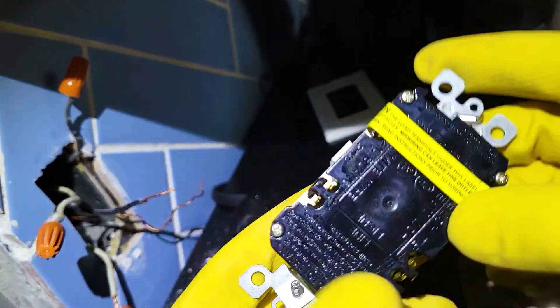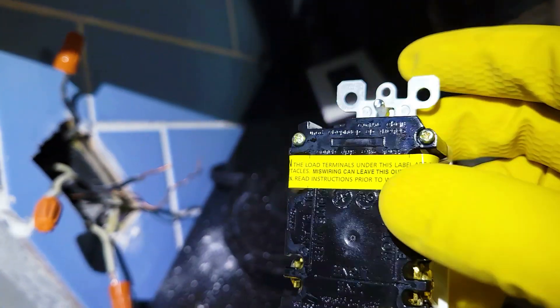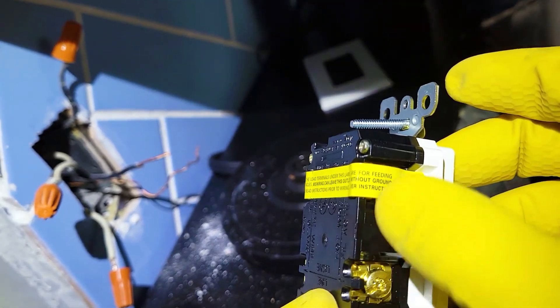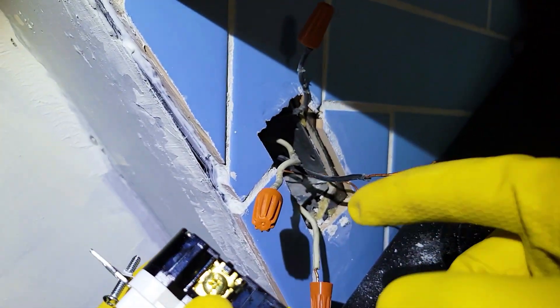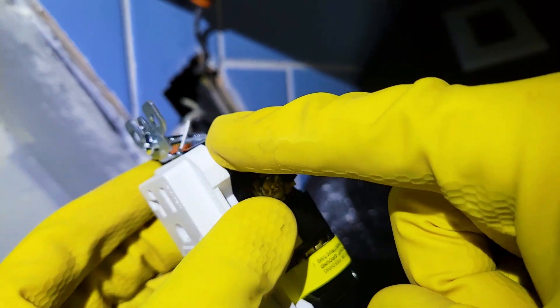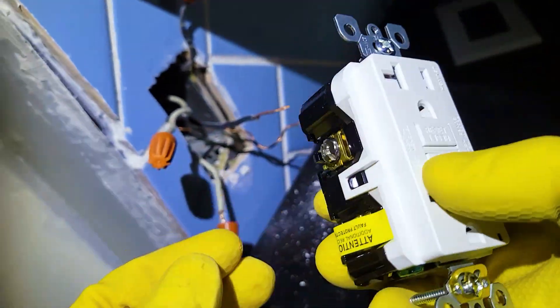There's this little label here that says attention: the load terminals under this label are for feeding additional receptacles. Miswiring can leave this outlet without ground fault protection. This is what we're talking about here—we've got two extras that are taking the power from this one once it's connected and feeding it to the next circuit down the road.